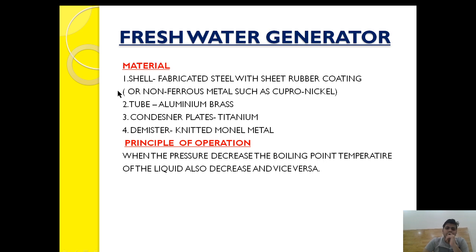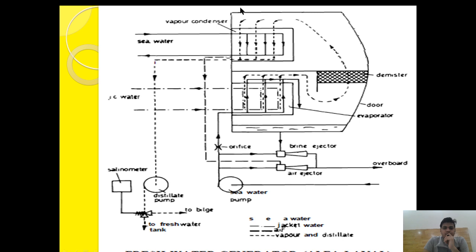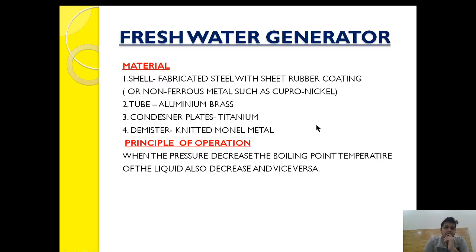The fresh water generator material basically consists of four things. First, the shell — the shell is made up of fabricated steel with sheet rubber coating. The idea is to use a shell which is of non-ferrous metal, because we are using sea water as a component for generating fresh water. If it is ferrous metal it will cause corrosion, so we use fabricated steel or non-ferrous metals such as copper-nickel with rubber coating to avoid any chances of corrosion.